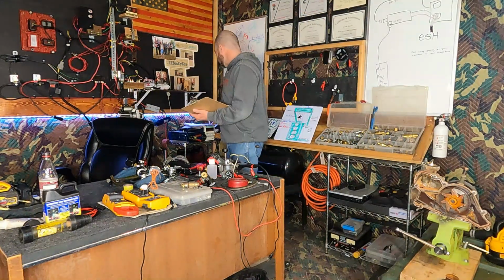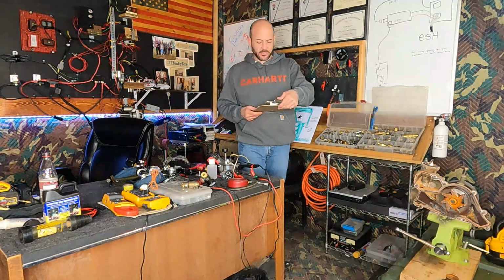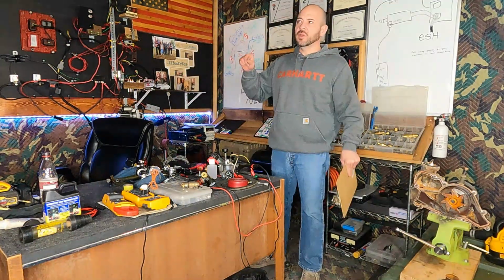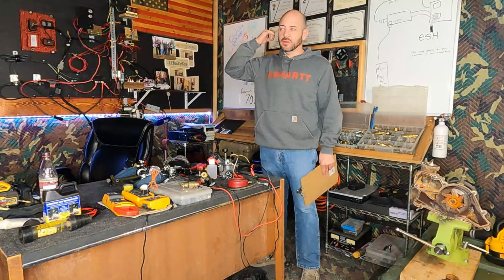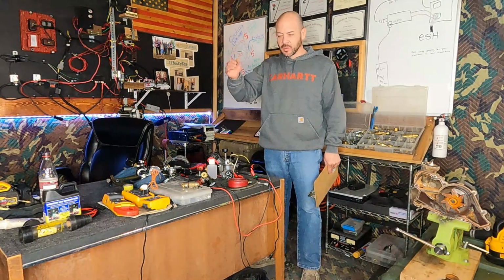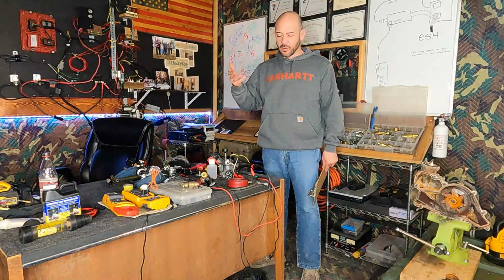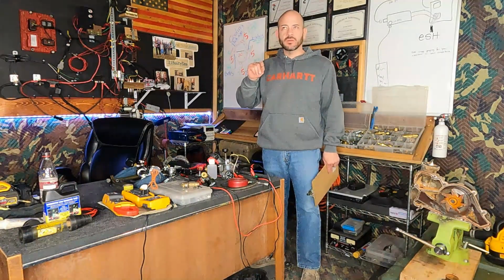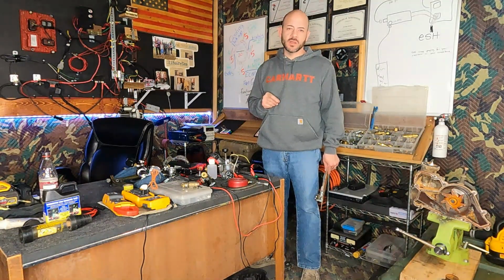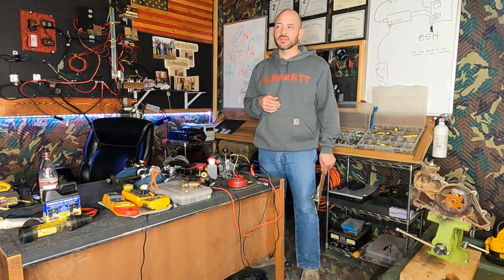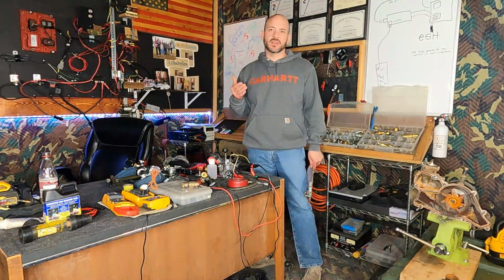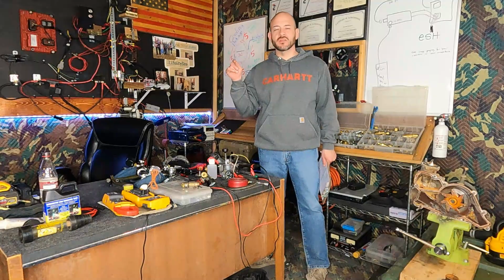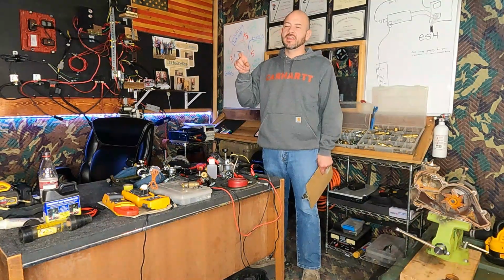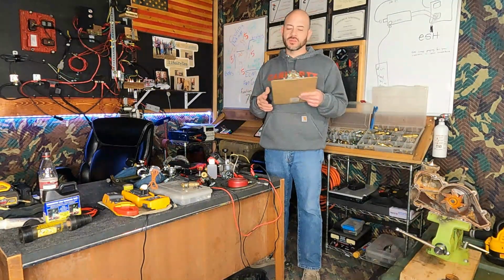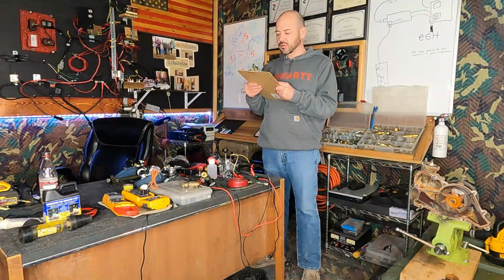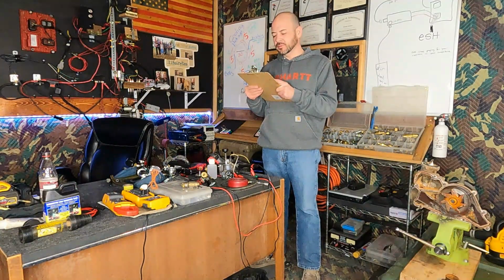Okay, oil coolers. Like I said, we're looking for about 7 to 25 degrees difference between one fluid and the next. We can look at oil temp and coolant temp on our laptop, and they should be within about 25 degrees. There can be a little bit more, like I said, on big trucks it's a little bit more.